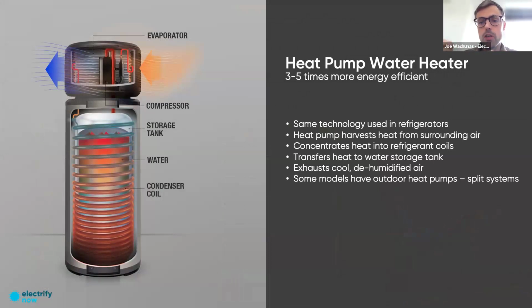Basically, it's a compressor on top of an electric water heater tank. The compressor harvests heat from the surrounding space the water heater is in, concentrates that heat into refrigerant coils wrapped around the tank, and transfers that heat to the water. It doesn't exhaust any pollution, just cool air. Heat pump water heaters need some air to breathe—we'll talk about that in a second—but they don't exhaust anything like NOx or other pollutants the way fossil fuel water heaters do.